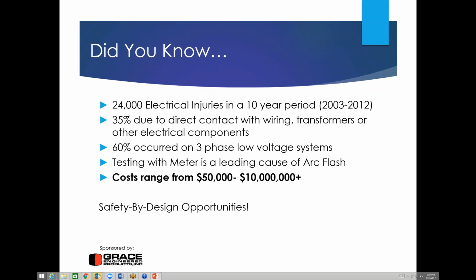And over a 10-year period from 2003 to 2012, we had about 24,000 reportable injuries, and beyond that, we don't know how many may not have been reported. But 35% were due to direct contact with wiring, transformers, or other electrical equipment. And probably even more surprising is 60% of these occurred on 3-phase low voltage systems. So going back to what John said, it's less than 600 volts, more commonly even at 480. And unfortunately, testing with a meter is a leading cause of arc flash incidents, and the costs range dramatically, but anywhere from $50,000 on up.